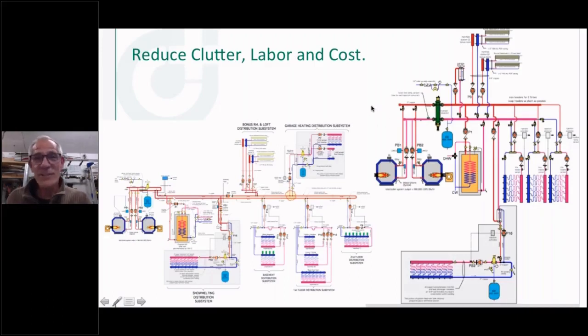Now, do you need one on every single boiler that you put in from this day forward? No, you don't. I'm going to tell you that right now. If you're putting in cast iron boilers that have wide open passageways, really there's not a lot of value to add in the hydraulic separator. Yeah, you'll get your air and dirt magnetic function on it, but the boiler's going to be fine just pumping through it. Some of the new fire tube boilers under certain conditions can get away without it if you can assure whatever distribution flow rate is going on there covers the flow rate that the boiler manufacturer wants through the boiler. Then you could just direct pipe it right from the boiler to the load.